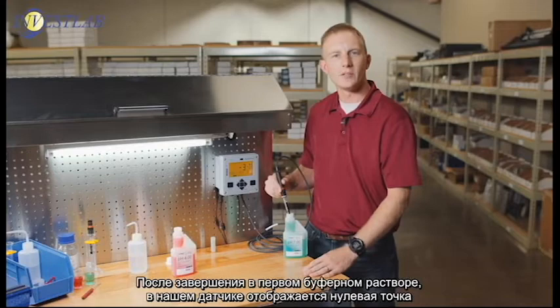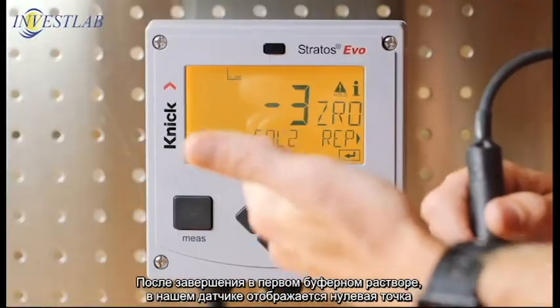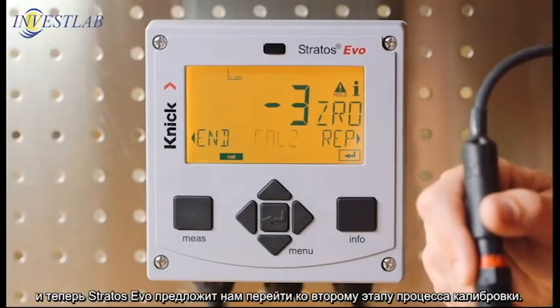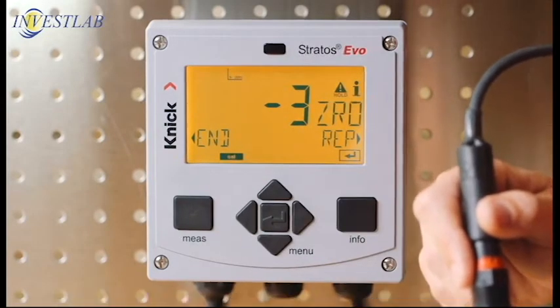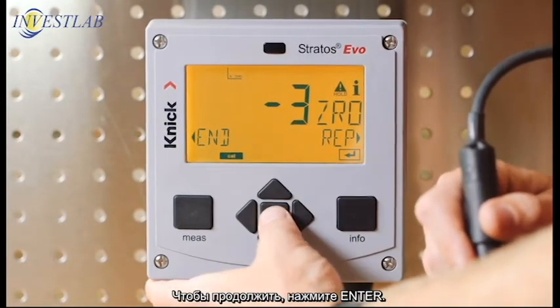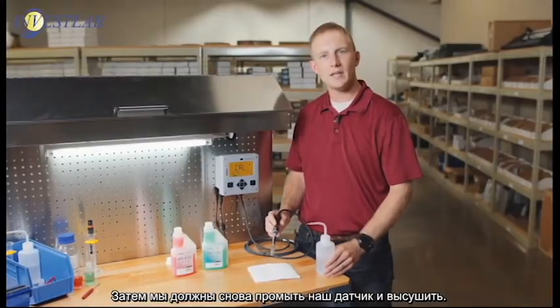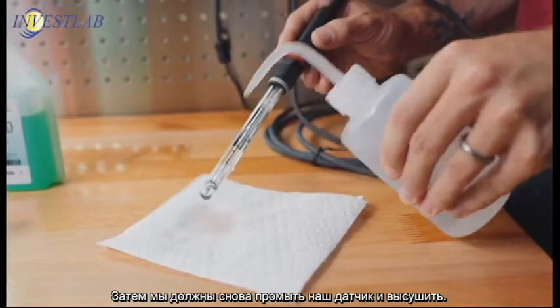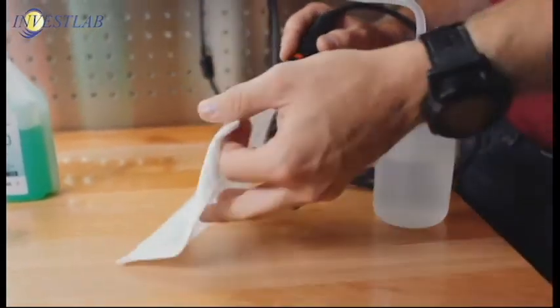Once completed in the first buffer solution, the 0 point of our sensor is displayed, and the Stratos Evo now prompts us to move to the second step in the calibration process. We'll press enter to continue. Next, we should again rinse our sensor with distilled water and dab dry.